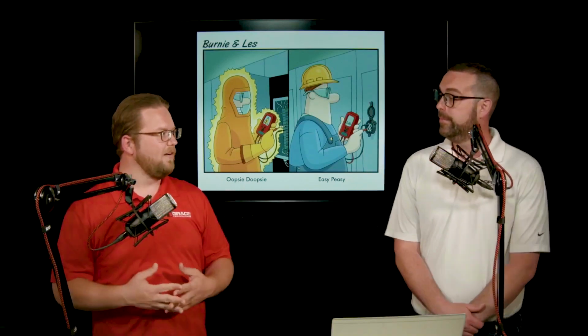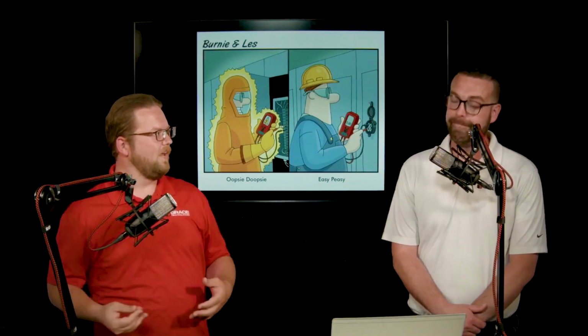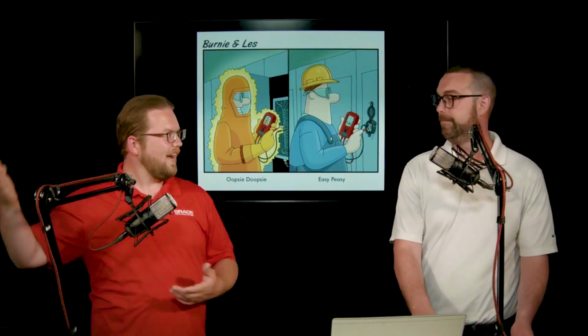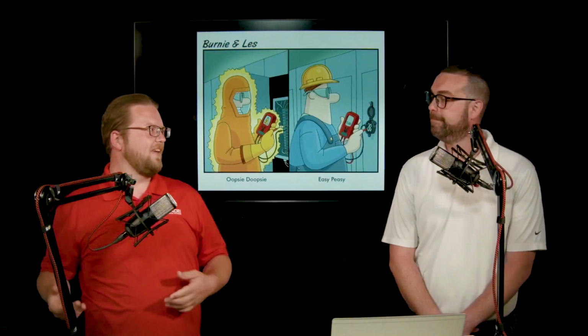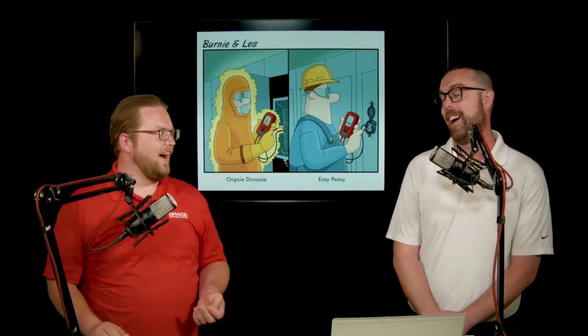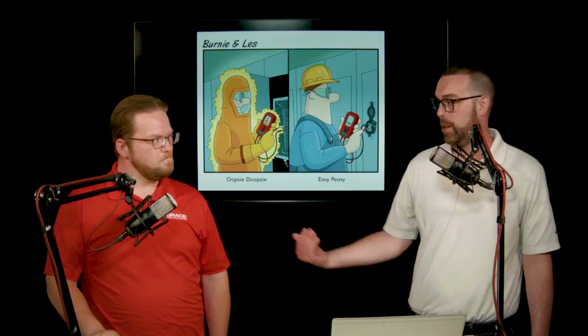A lot of what we're focusing on, though, is that the majority of reported accidents happen with low voltage equipment. I don't know if it's because people are more cautious with the high voltage on those lines, and then once inside they think, oh, it's just 480, 600 volts, not as high as working on a power utility or a transformer outside bringing that voltage in.